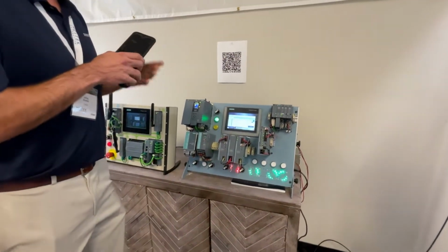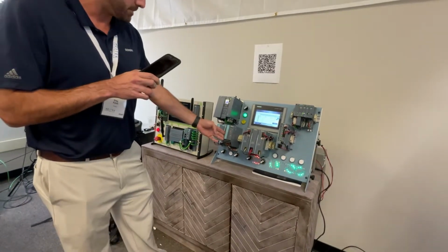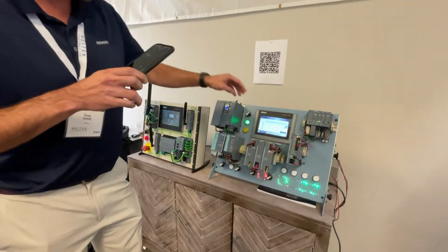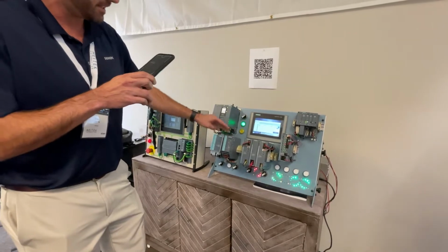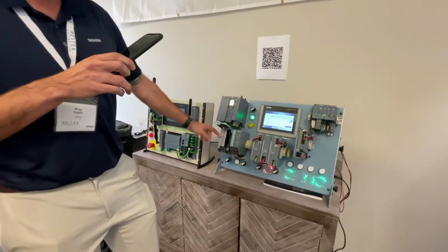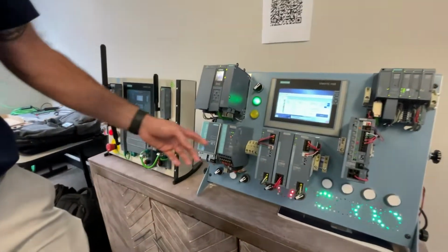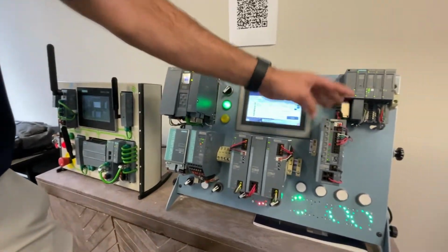Then last but not least, if we need to do some backup, we have a UPS module. So basically the power supplies are feeding this UPS module. This is conditioning the battery. This right next to it, it's a 24 volt battery, before it provides output to the selectivity module and all the different loads.